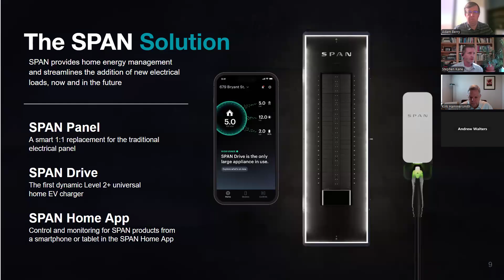Looking back through the code cycle history, EMS was first brought into the National Electrical Code as a concept as far back as 2014, primarily for EV charging. The main application was to use a CT on the main service and curtail the EV charger if you started to exceed the capacity of the service.